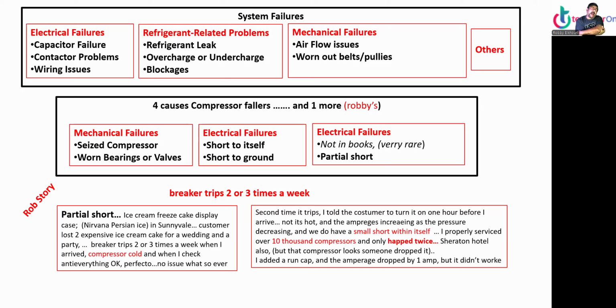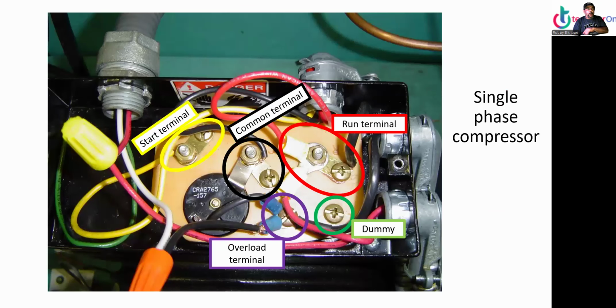I've probably serviced over 10,000 compressors in my life, and it only happened twice. Sheraton Hotel and that Nirvana ice cream. But at Sheraton, the compressor failed. That was bad. I added a run capacitor. Amperage dropped by 1 amp, but it didn't work. So it only happened twice, very rare, but we do have a partial short, right? They say broken valve or seized, locked, short to itself or short to ground, but we also have a partial short. Very rare, but it could happen. All right, now let's move on.